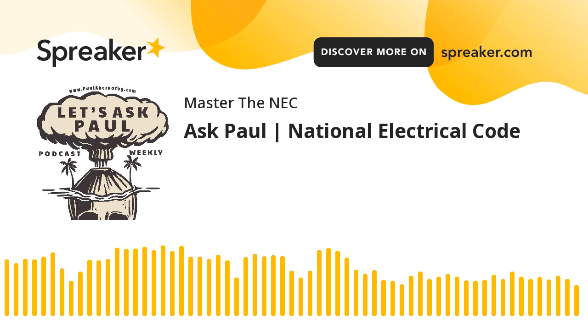If everything in the equation, the device that you're terminating to and the lugs, is rated 90, then you most certainly could use the 90. But here's the problem. Typically, lugs aren't rated 90. Okay? They're rated 60/75.